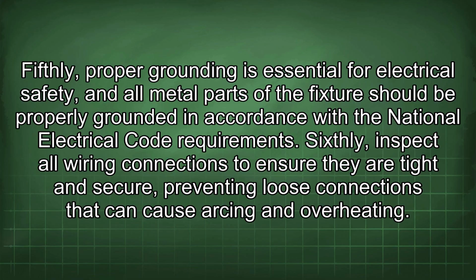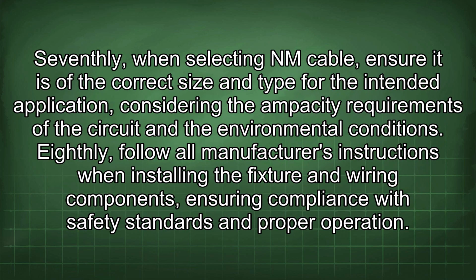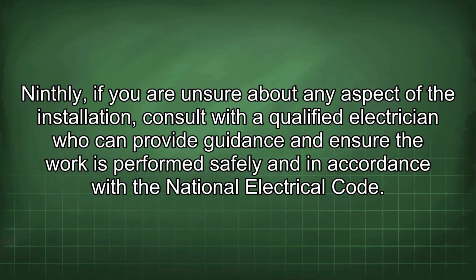Sixthly, inspect all wiring connections to ensure they are tight and secure, preventing loose connections that can cause arcing and overheating. Seventhly, when selecting NM cable, ensure it is of the correct size and type for the intended application, considering the ampacity requirements of the circuit and the environmental conditions. Eighthly, follow all manufacturer's instructions when installing the fixture and wiring components, ensuring compliance with safety standards and proper operation. Ninthly, if you are unsure about any aspect of the installation, consult with a qualified electrician who can provide guidance and ensure the work is performed safely and in accordance with the National Electrical Code.